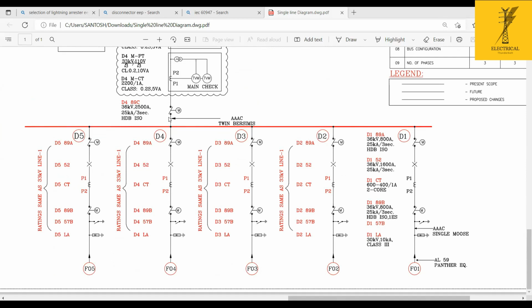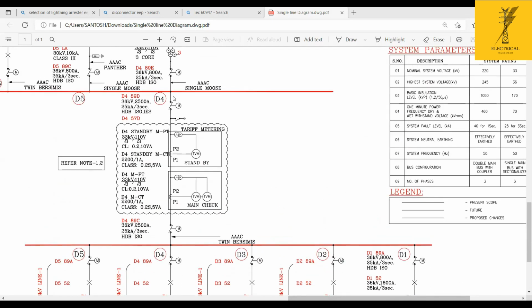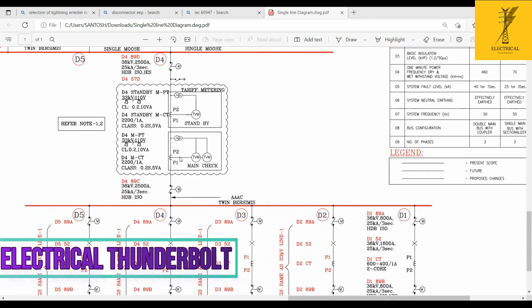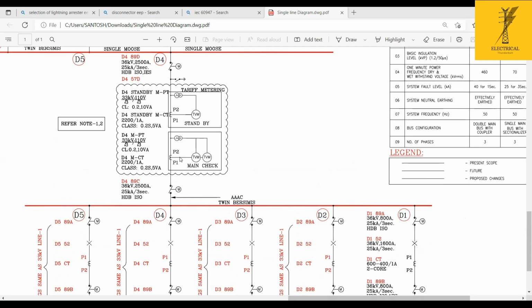In substations, it is fine because we have plenty of gantry towers which can bear the weight of this conductor. In the transmission line, it is not possible. So this is the twin moose. And in some projects, you do not have the tower structures to carry this AAAC twin moose. In that case, you will go with a rigid bus like an aluminum bus of 4-inch or 3-inch, depending upon your current rating and other factors. So that is the way of doing the selection of the conductor.